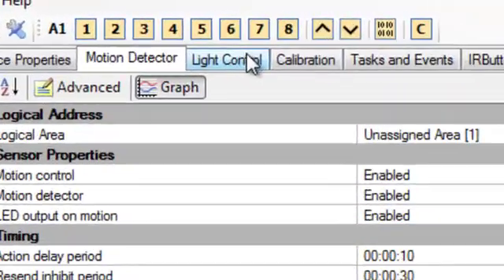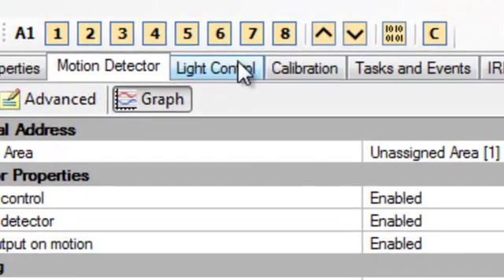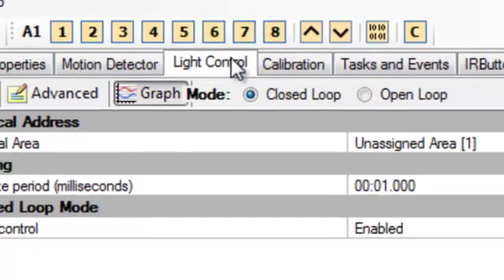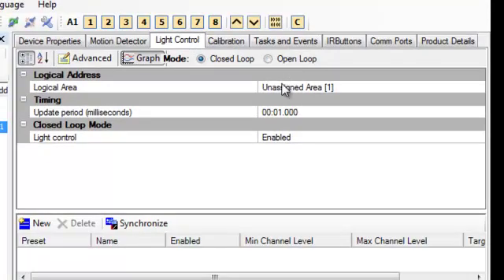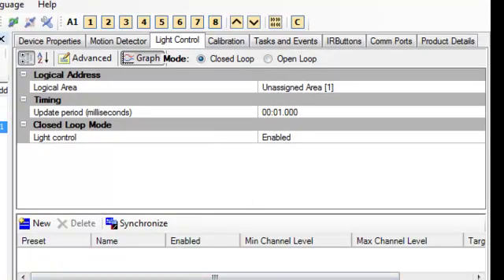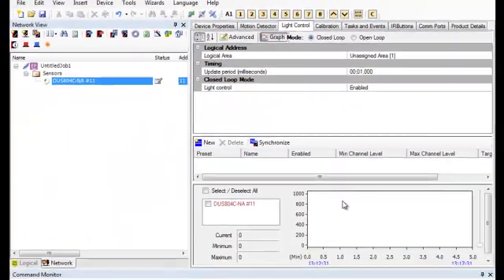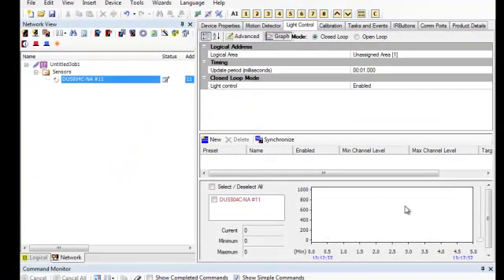Also, within here we have light control. So you can do closed loop or open loop daylighting. And again, this is going to be based off of presets. But because you have that photo sensor, you can actually see the lux levels and decide what bands that you're going to put in here so you know how the lights are going to react based on the lux levels.